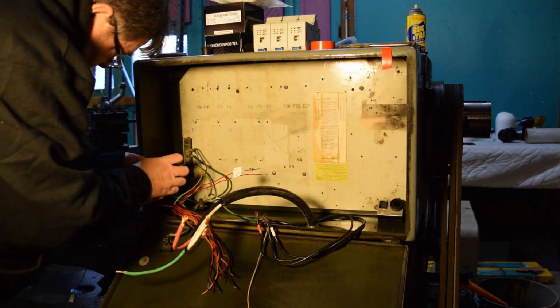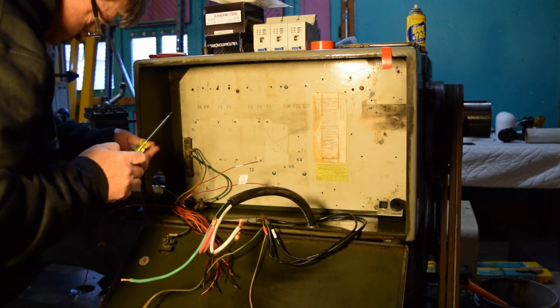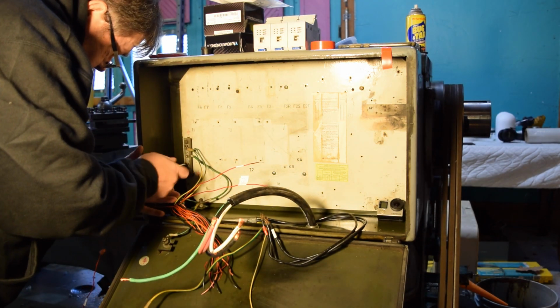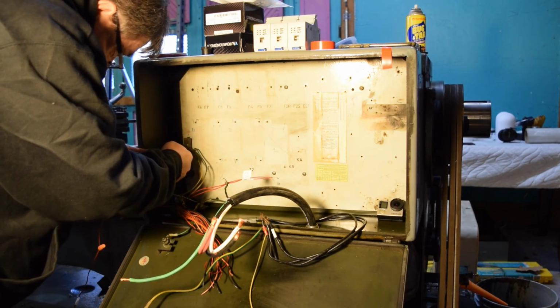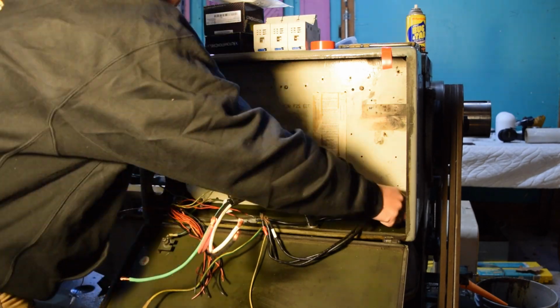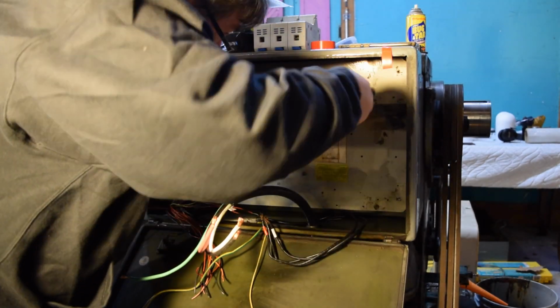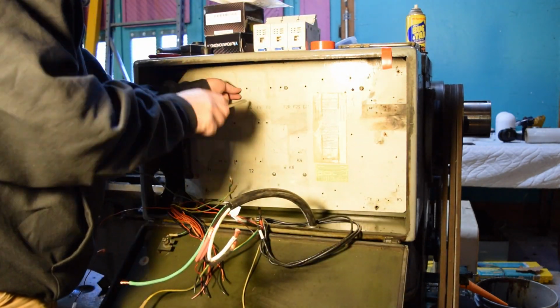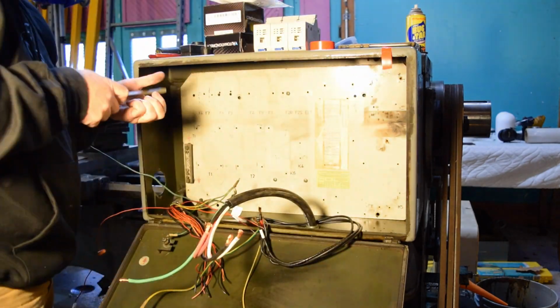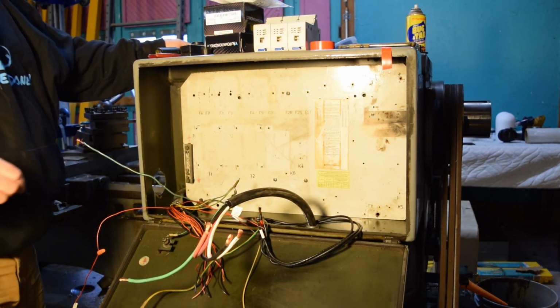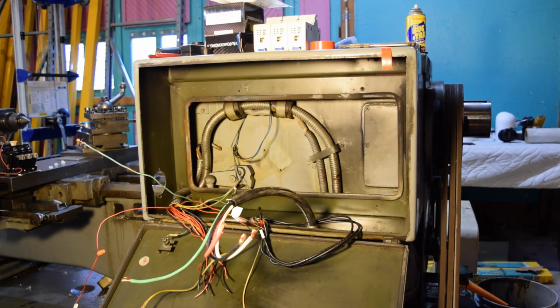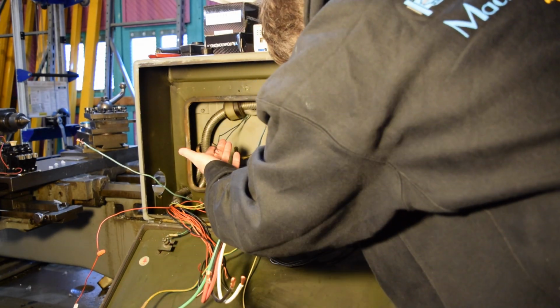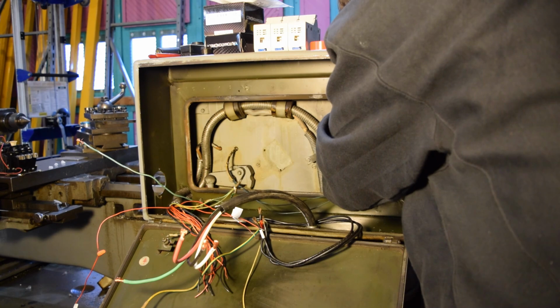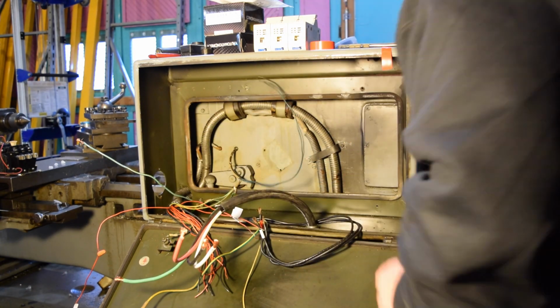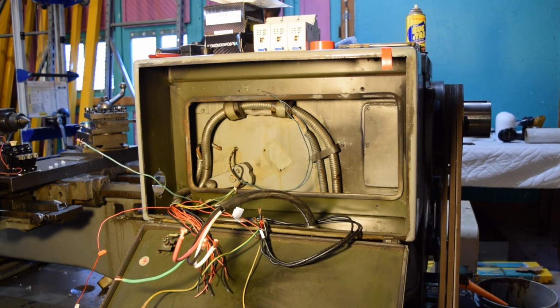Got the contactor pulled out there. A few more wires to disconnect on this ground bus, and we can get this panel out of here. Well, would you look at that? More wires. I don't know where they go. There's two green wires coming out of the middle of the gearbox. Not sure where they go.